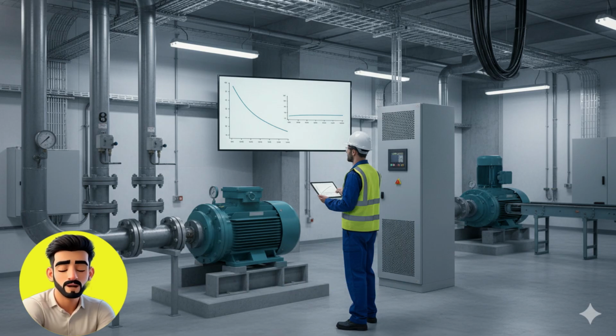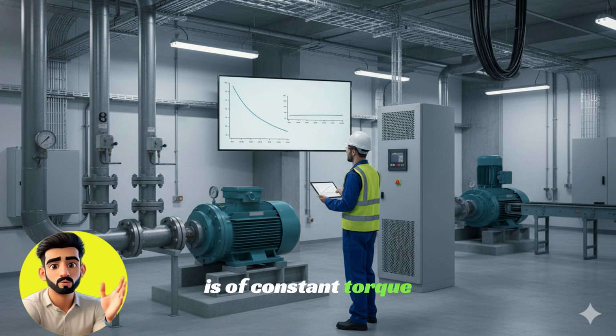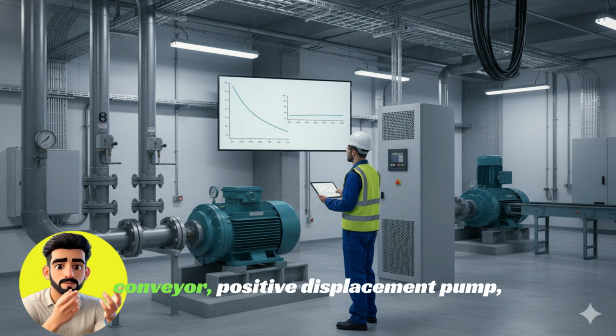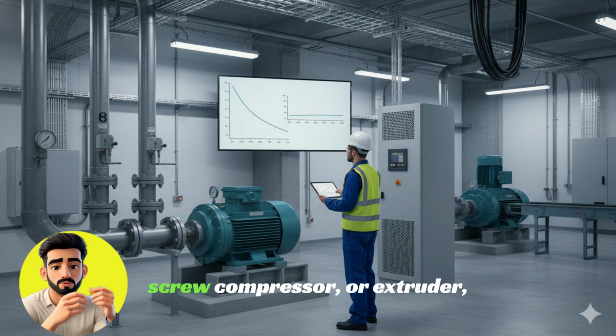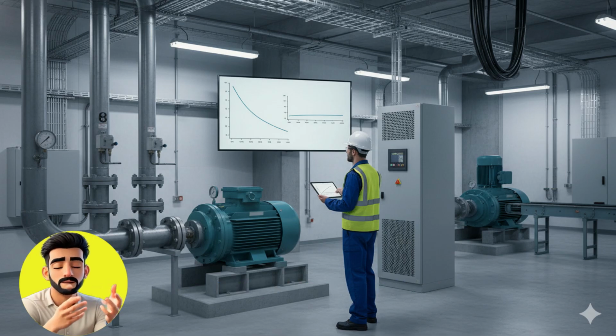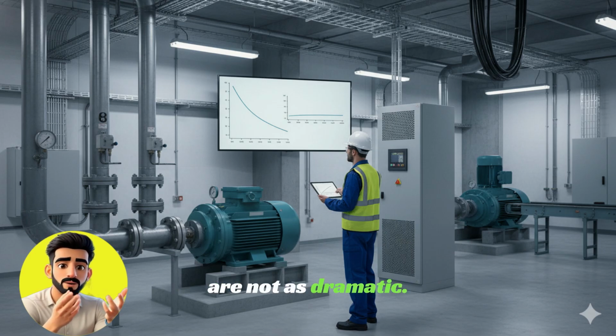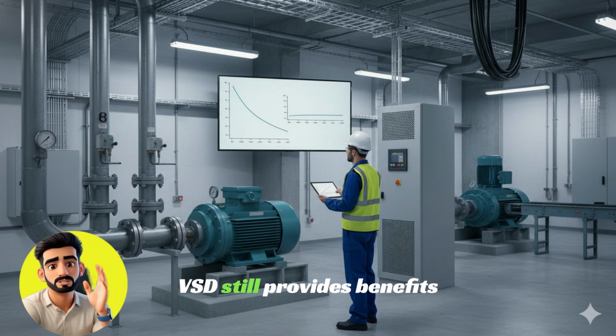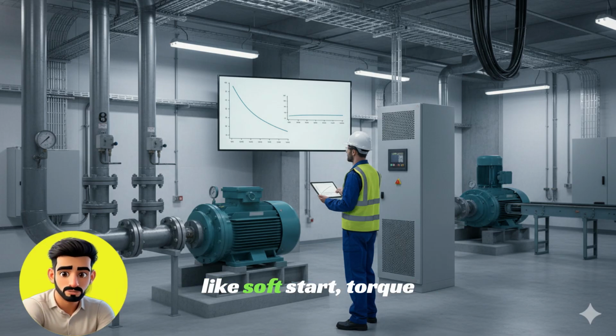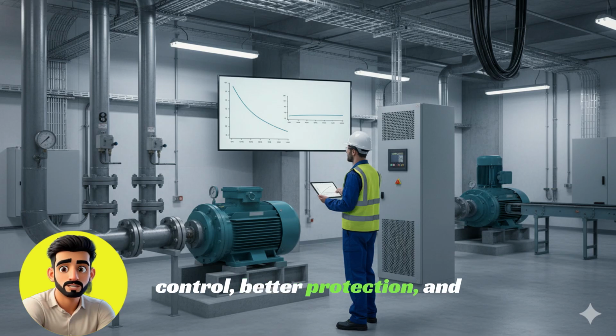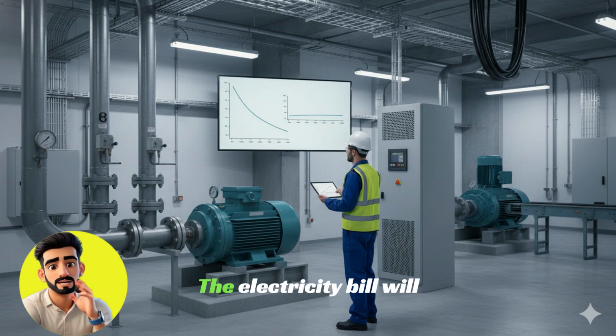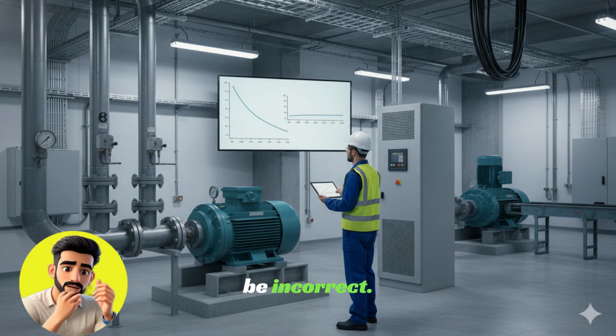Everyone is happy. However, if your load is of constant torque type, such as a conveyor, positive displacement pump, screw compressor, or extruder, then the energy savings are not as dramatic. VSD still provides benefits like soft start, torque control, better protection, and process flexibility, but expecting the electricity bill to be halved would be incorrect.